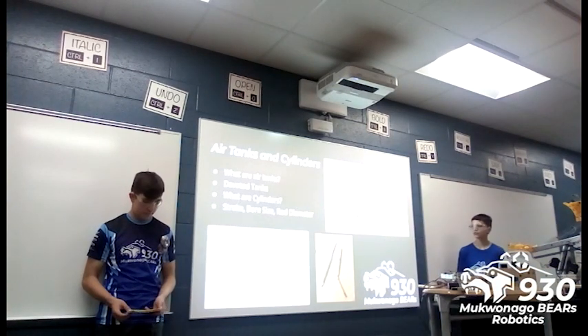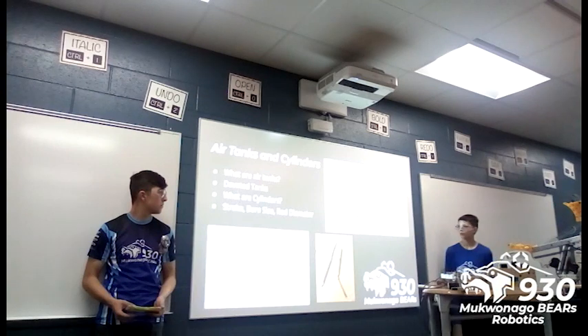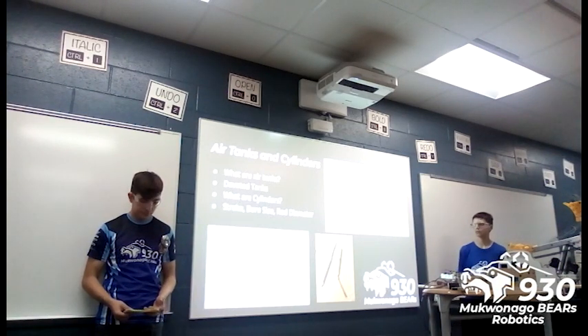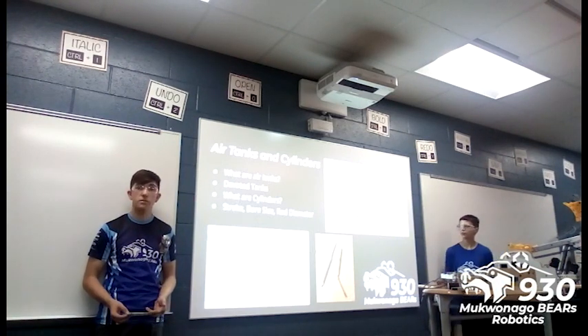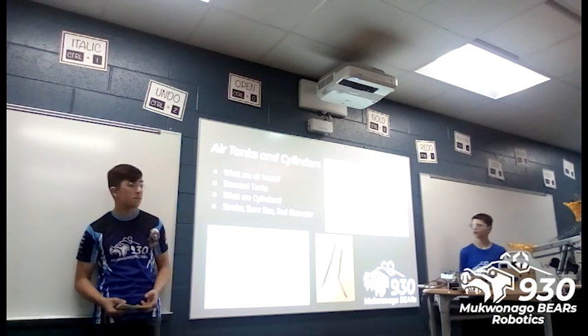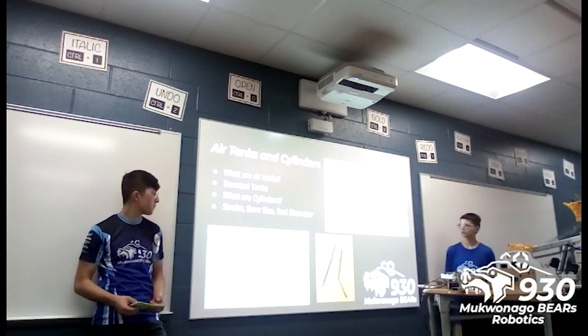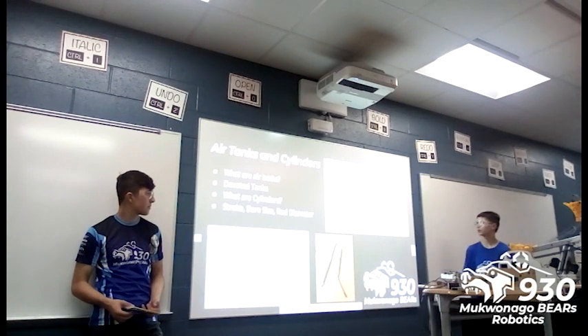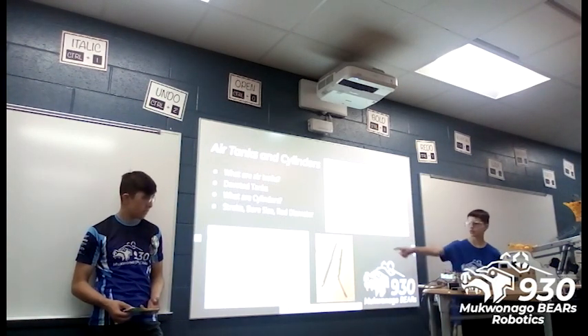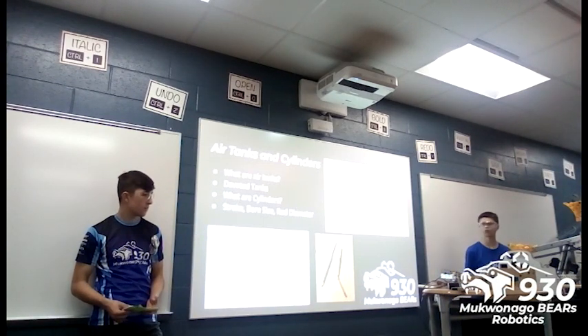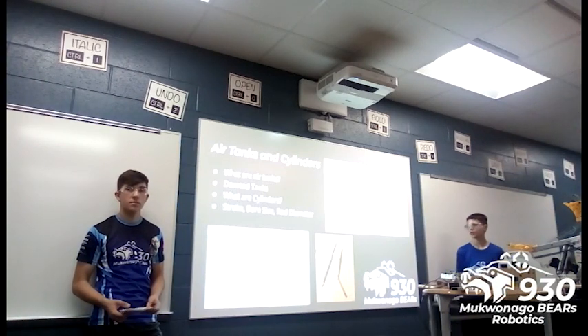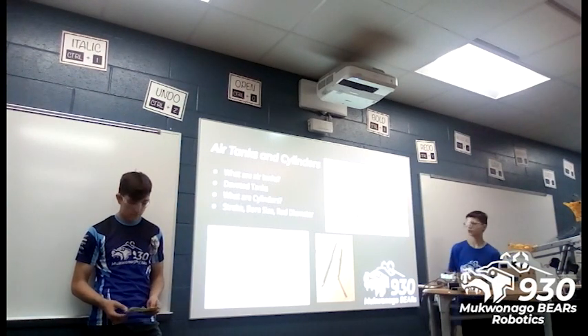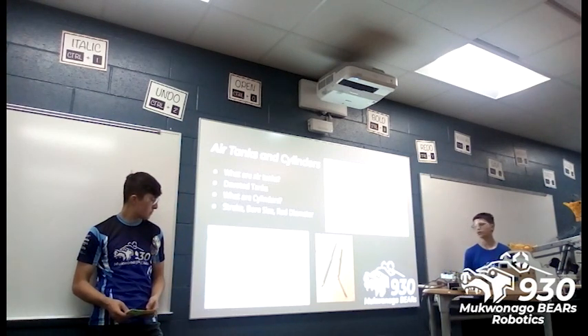The main ways cylinders differ are stroke, bore size, and rod diameter. Stroke is the difference between the cylinder's extended length and retracted length — how far the piston will extend. A larger stroke means a larger piston using more air. Bore size is the inner diameter of the piston; a larger inner diameter means a larger cross-sectional area, which determines how powerful your piston is. A larger cross-sectional area means more force — so the extend mode is actually stronger than the retract mode, because the rod takes up part of the surface area on the retract side.